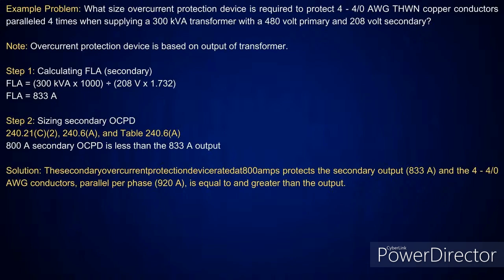If I have a 300 kVA transformer, I want to put it in VA, so I multiply by 1,000. Then you have 208 volts times 1.732, that'll be 360 volts. You divide that in, and that's going to give you 833 amps. Now, this is interesting. Why didn't I go up to a 900 amp overcurrent device? Well, 240.4(B) is for devices up to 800 amps. But once I look at 240.4(C), the conductors have to be equal to or greater than the output. My output is 833 amps, which means I'm going to drop down.